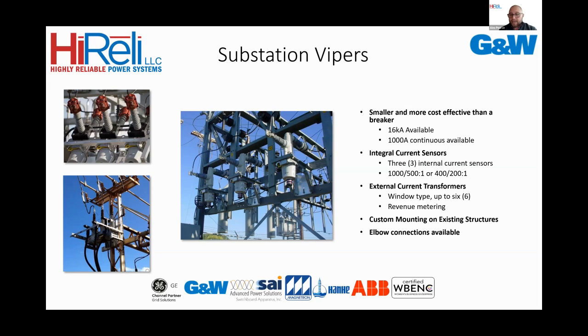If you need a different accuracy level or a different CT ratio, or maybe even a different input, the internal sensors have the 1 amp input. We can do external window transformers, as you can see in the top left picture. Because this is a dead tank construction with the Viper, we can slide those window CTs right over the bushings. That can get you your metering grade accuracy, your 5 amp secondaries, whatever you might need at the substation. We can also custom mount to existing structures, as you can see in the right picture. All we need is drawings of what you want us to mount to, and we can come up with custom frames to mount on there.